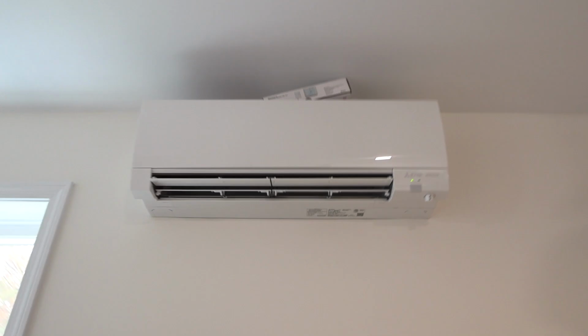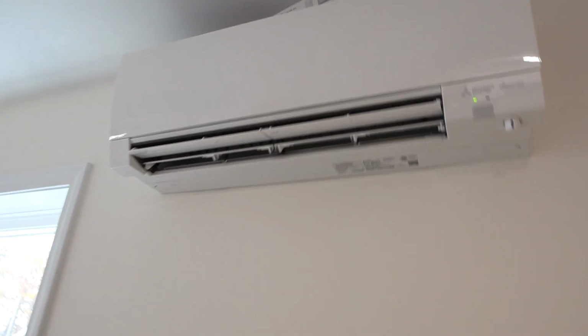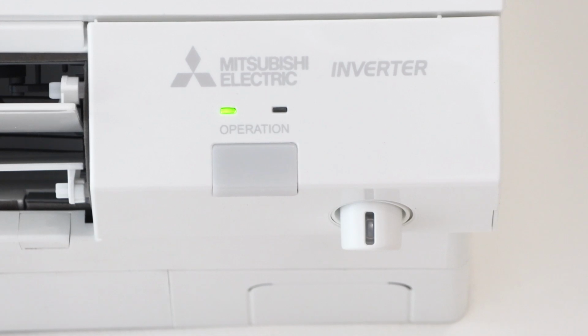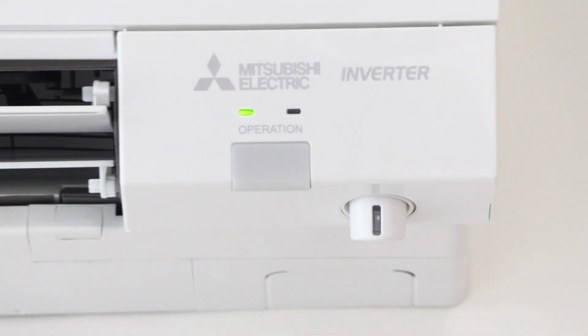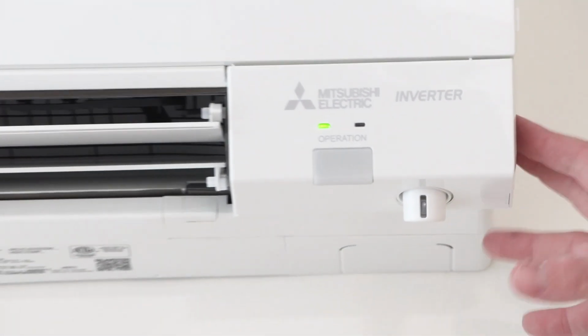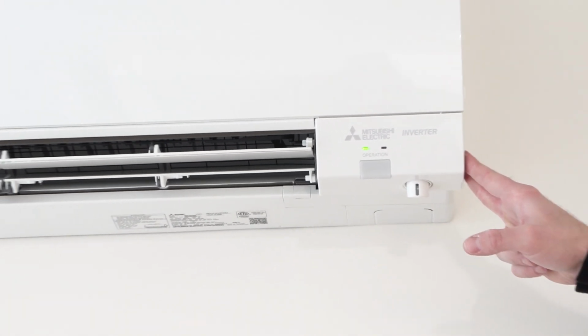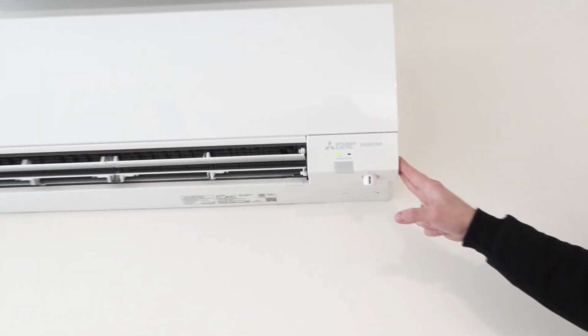And so, you know, if your house gets too cool, then you turn up the heat really high, and then it heats it up too warm, and then you turn off the heat and it gets too cold again. And so with a system like this, you just want to leave it the same all the time. You don't want to leave the house and drop it down to 64 or 60 or whatever your set point is, because the system is not built to dump so much heat that it can heat it back up to 68 later. You just leave it and it will still use less energy than if you're doing that cycling up and down.